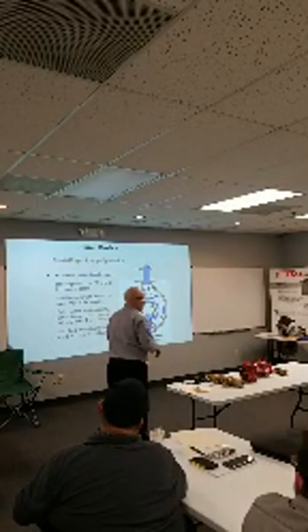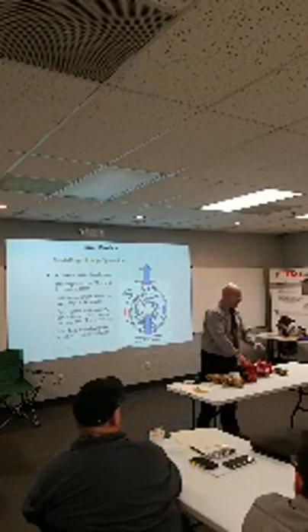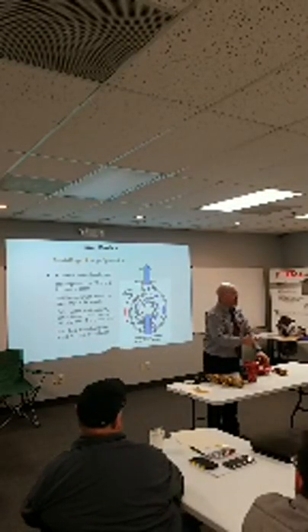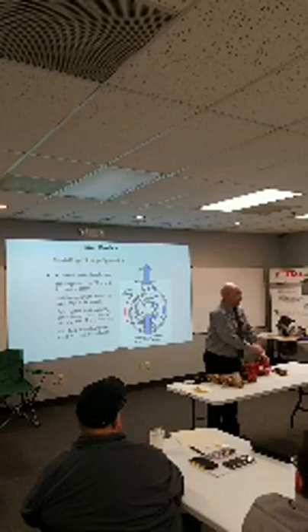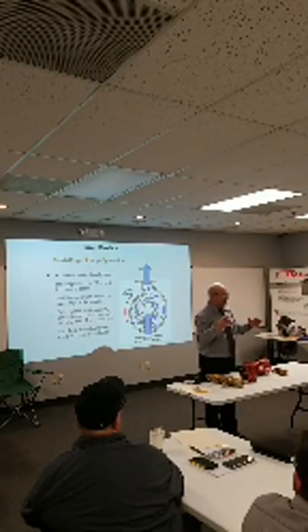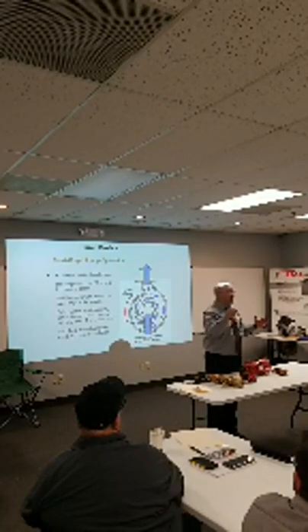Do you have a picture of a discharge control valve? Are you talking just like an isolation valve? Well, a balance valve is better. If you just use a gate valve, over time, it's going to wire draw, and you're not going to be able to shut it off. So a globe-style valve is good, or they make balance valves. Or in commercial jobs, we use what we call a Flotrex valve. It's a triple-duty valve. It's got a check valve, a balancing valve, and it's got meter ports on it. So there are valves that you use.